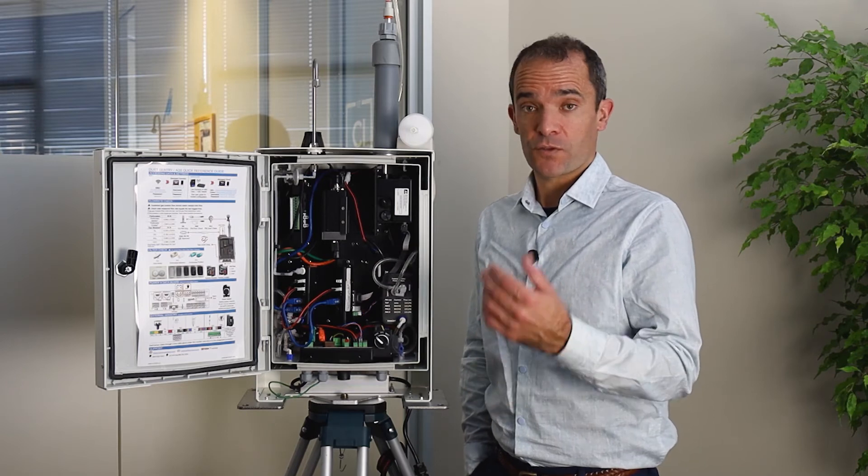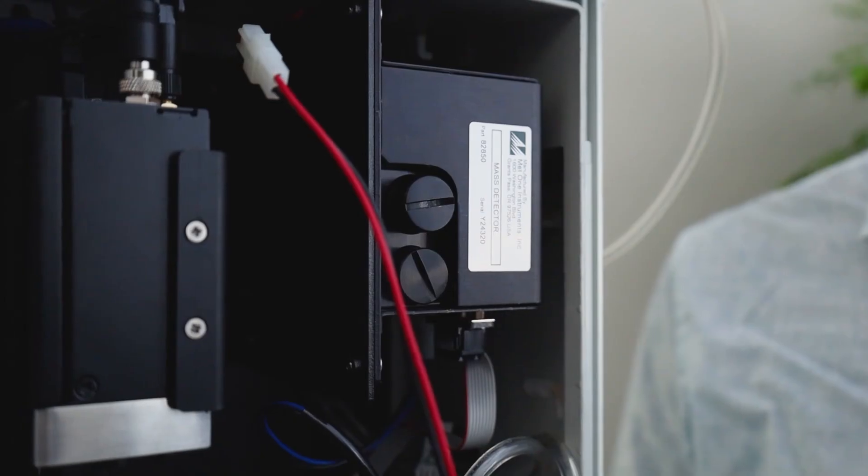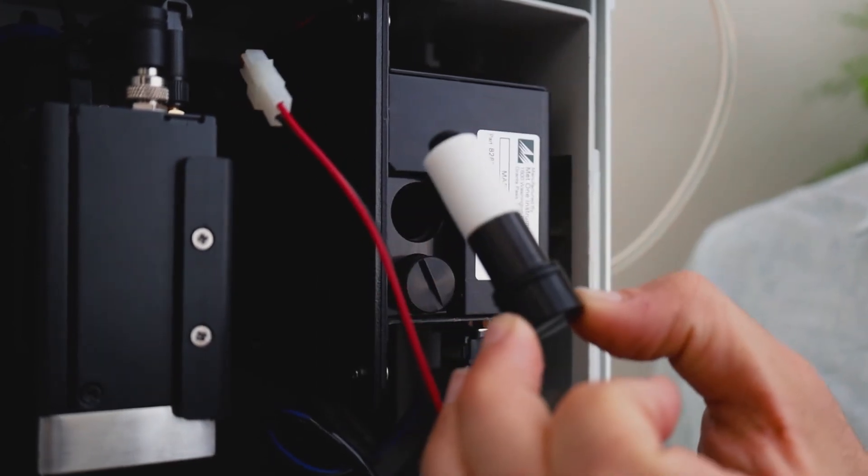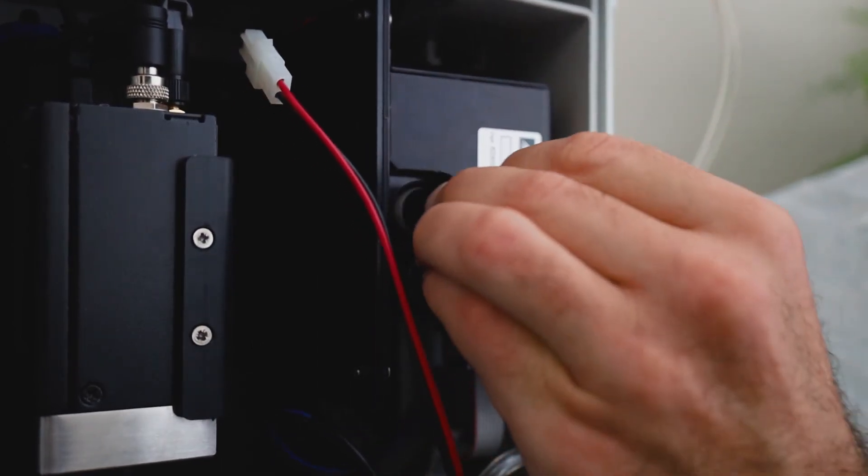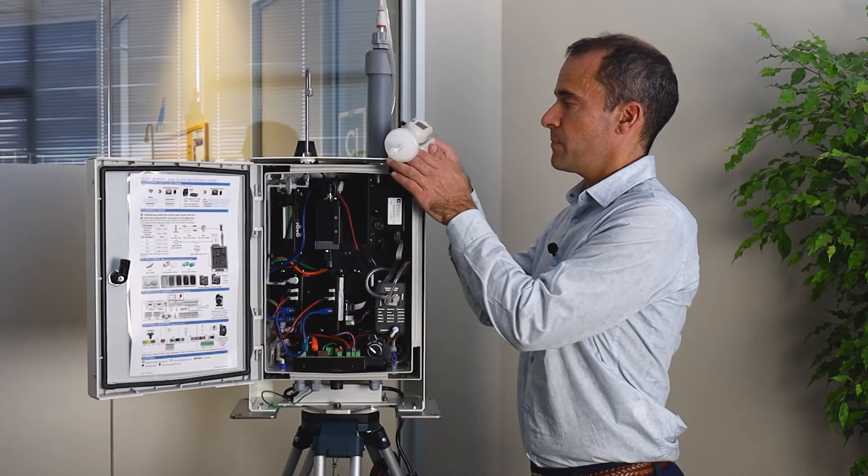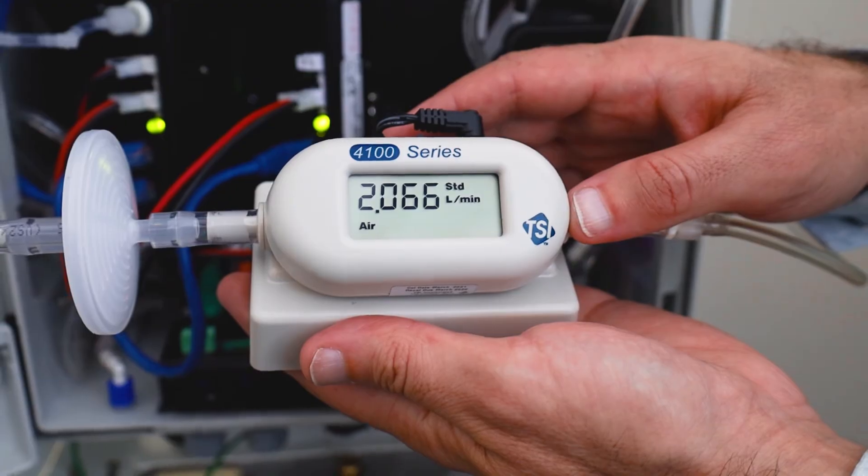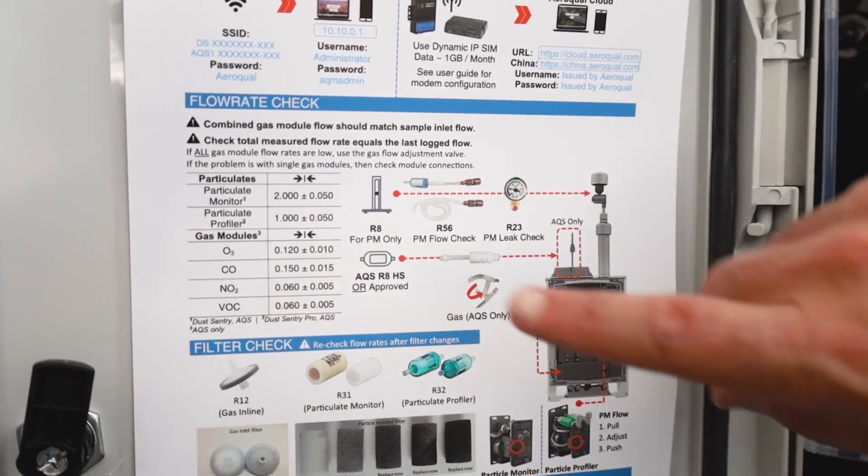After you've changed the engine, it's really important to make sure that you've got clean filters, whether it's the particle engine or the particle profiler. The next step is to set the flow rate appropriate for your engine. You'll be using the flow meter for this. The appropriate flow rate is given to you on the door sticker.